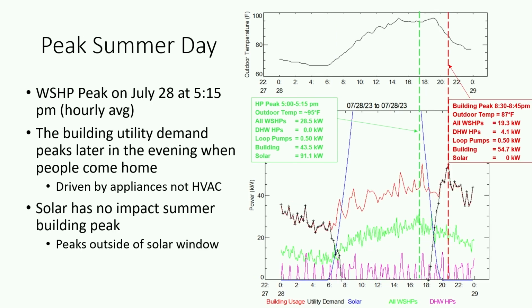Similarly, here's a summer day. Again, here's what the heat pumps were doing. Here's what the building was doing. Here's what the solar array was doing, and you can't see it very well, but the red is what you pull from the utility, and of course, when the sun comes out, the utility demand goes negative. But here is the peak demand on the water source heat pump system for space conditioning. Again, the building had a different peak.